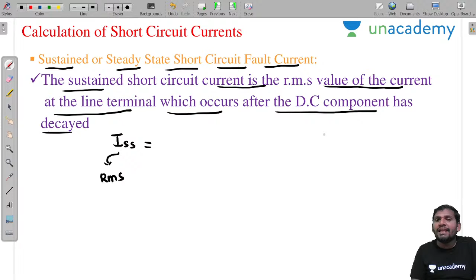After the DC component is decayed to 0, what remains is only the steady state short circuit current. The instantaneous value of short circuit current is Vm by Z sine of (omega t plus alpha minus theta). But we want only the RMS value. For a sinusoidal component, the RMS value is the maximum value divided by root 2. This gives the sustained or steady state short circuit fault current.